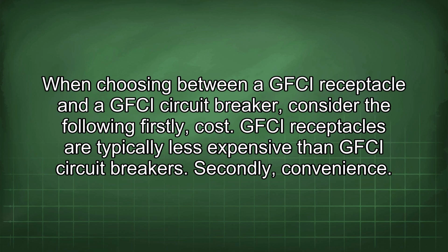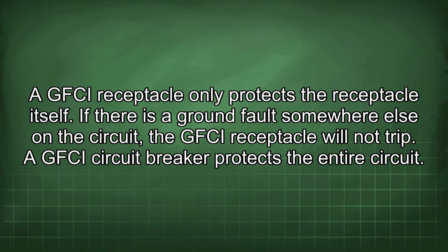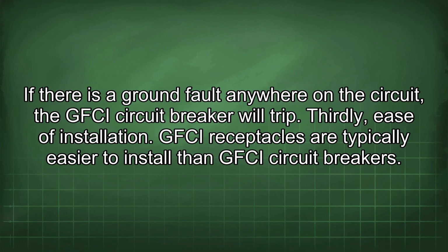When choosing between a GFCI receptacle and a GFCI circuit breaker, consider the following. Firstly, cost. GFCI receptacles are typically less expensive than GFCI circuit breakers. Secondly, convenience. A GFCI receptacle only protects the receptacle itself. If there is a ground fault somewhere else on the circuit, the GFCI receptacle will not trip. A GFCI circuit breaker protects the entire circuit. If there is a ground fault anywhere on the circuit, the GFCI circuit breaker will trip. Thirdly, ease of installation. GFCI receptacles are typically easier to install than GFCI circuit breakers.